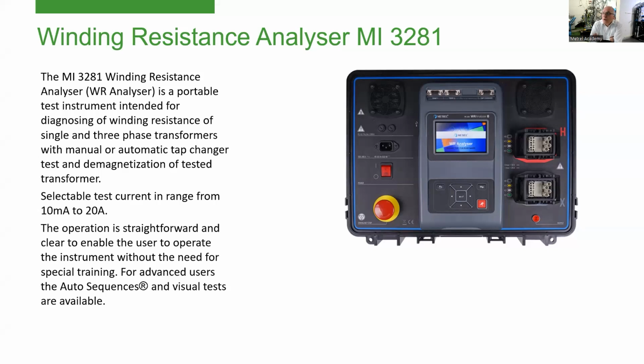It can be used for single phase or three phase transformers with tap changers or without, and especially, if this is a motor-driven tap changer, we can control the tap changer, so automatic tests can be done. And as usual with instruments from Metrel of this type, simple use, the user interface is already well known, so no big training needed. And for advanced users, auto sequences are also available.